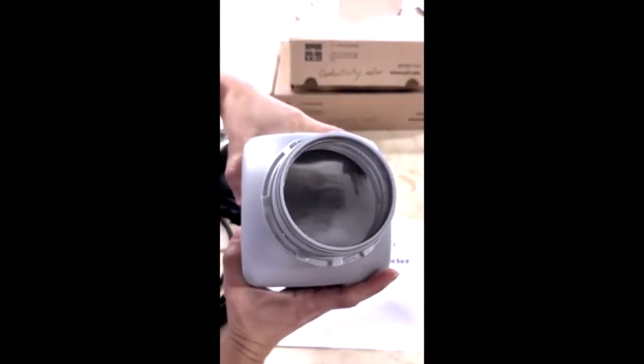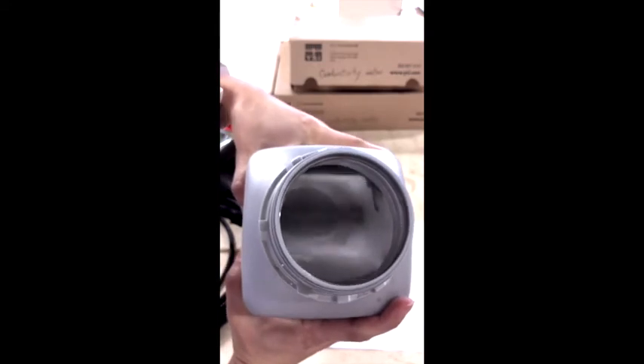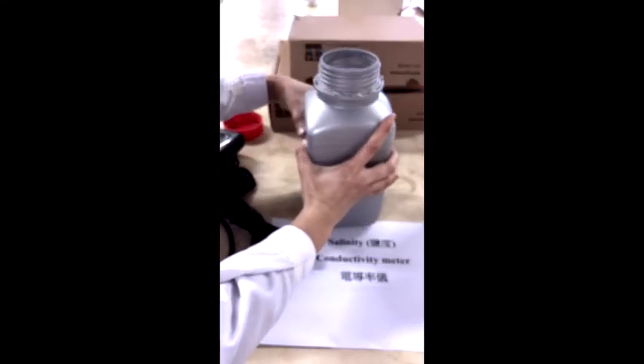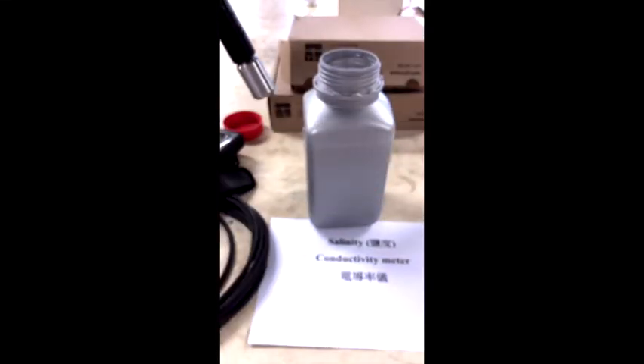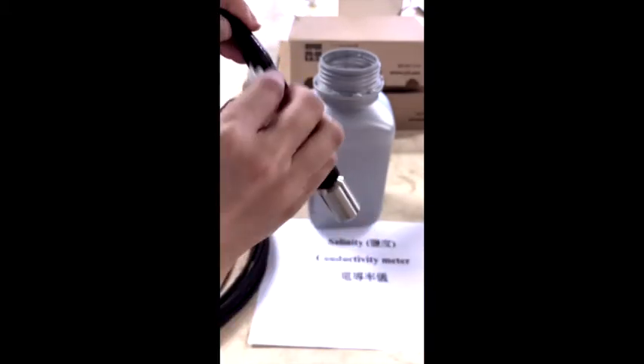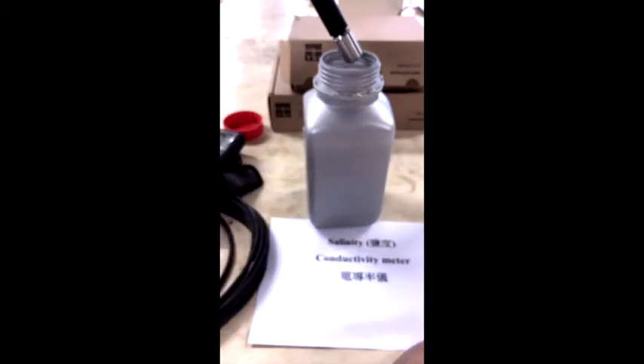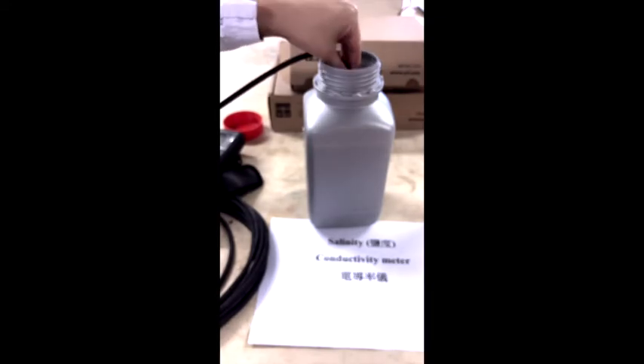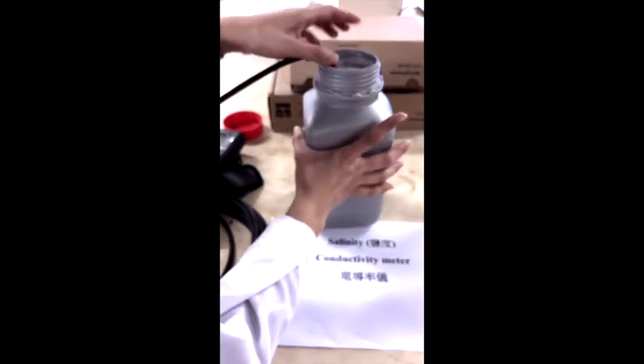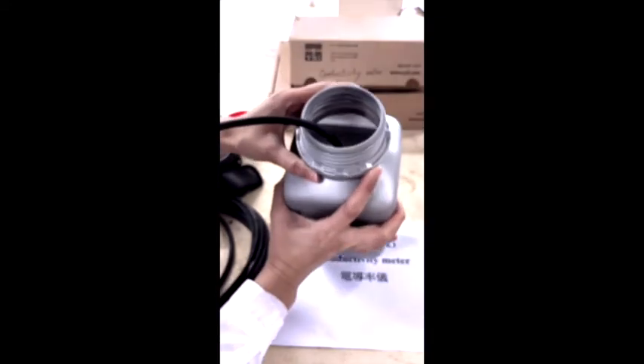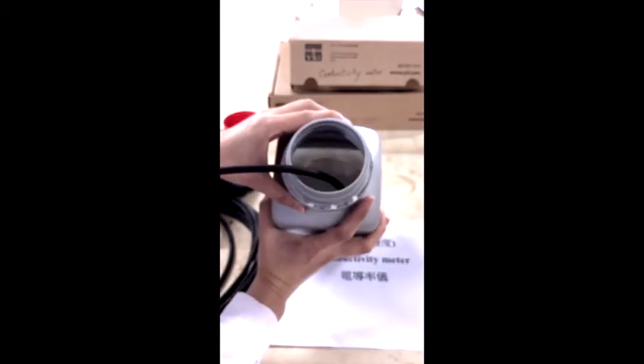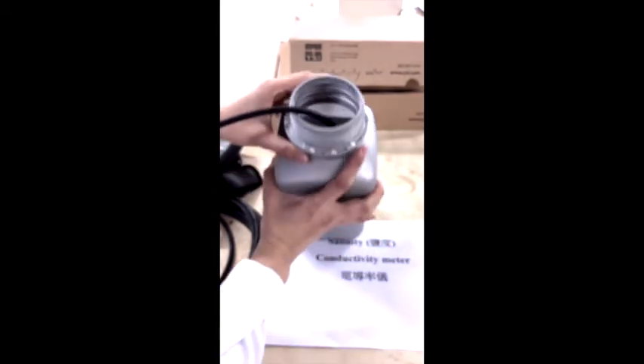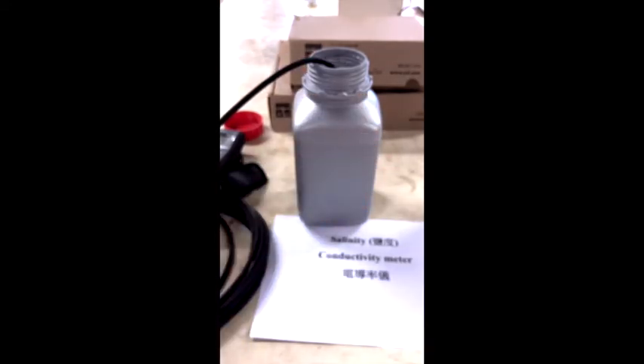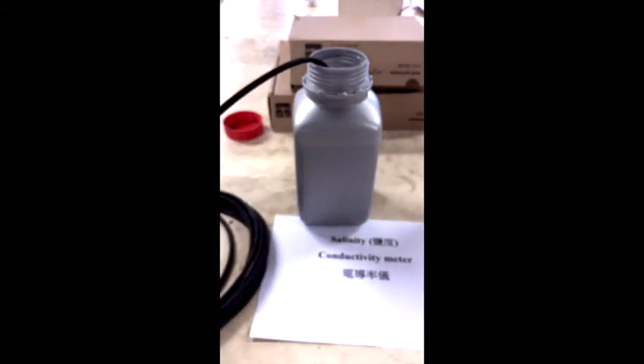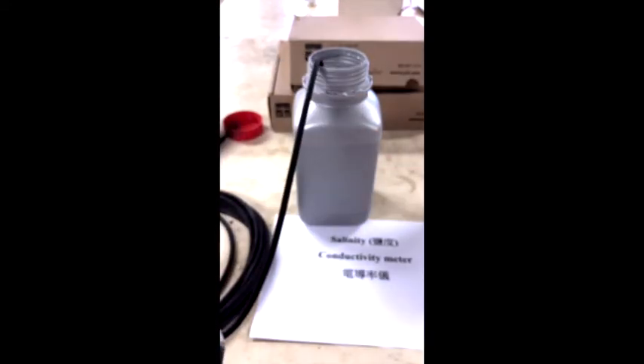As you can see, the reagent bottle is full of the seawater sample, and then we put the cleaned probe into the water sample. Make sure there's no surface water attached on the probe. Make sure that the probe is fully immersed inside the water sample. And now we can take the readings for the salinity.